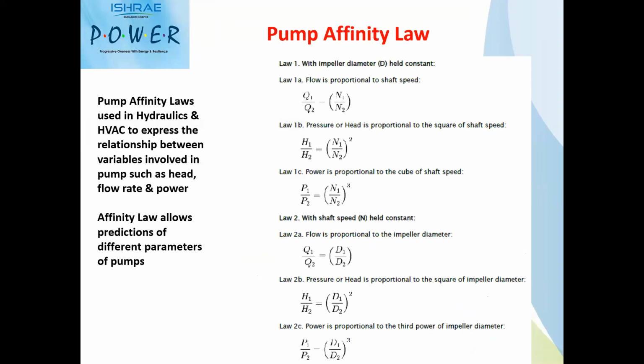So this is the basic pump affinity law which I was defining. This is a very basic law which correlates various parameters of the pump. Any particular pump, if you see, will have flow and head as basic parameters, then RPM if it is a variable speed application, then impeller diameter if it is a constant speed application, then the power drawn by the pump. The affinity law gives you the complete relation between flow, RPM, and impeller diameter with respect to your head and the power drawn by the pump.